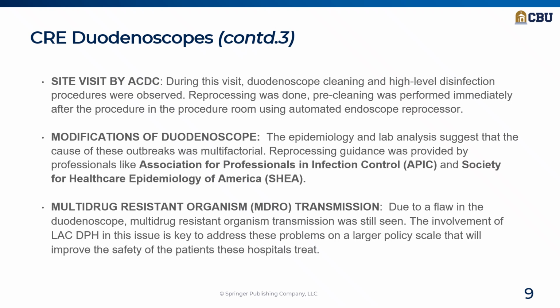Investigators conducted a site visit in 2015 to directly observe duodenoscope reprocessing. They reviewed cleaning and high-level disinfection procedures, confirmed that trained GI technicians and nurses were performing reprocessing, and noted that pre-cleaning occurred immediately after the procedures. The facility used an automated endoscope reprocessor and stored scopes appropriately.